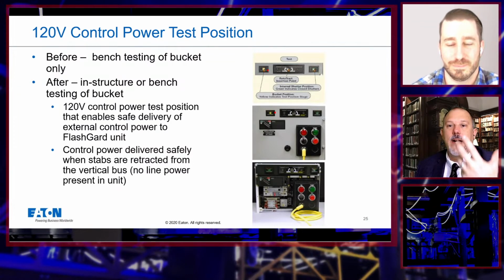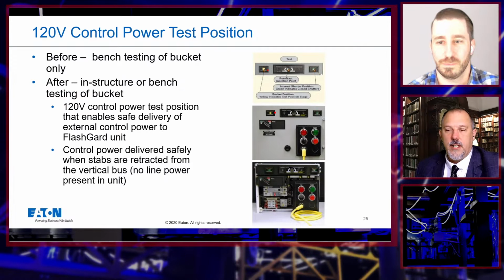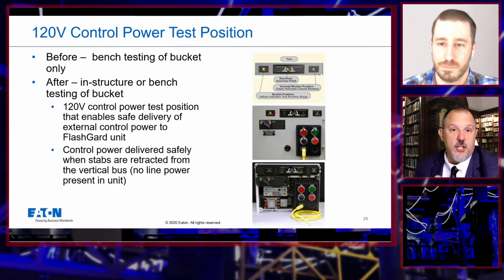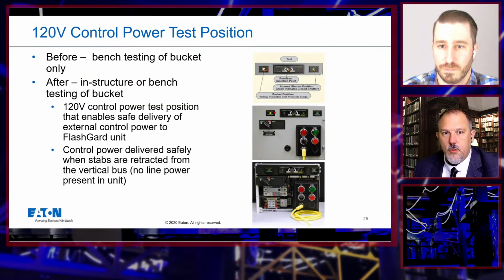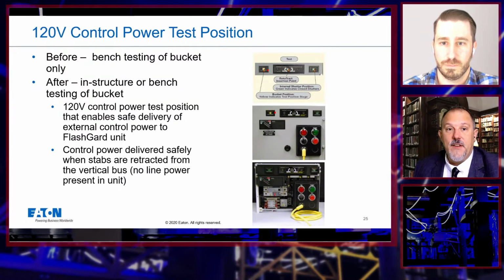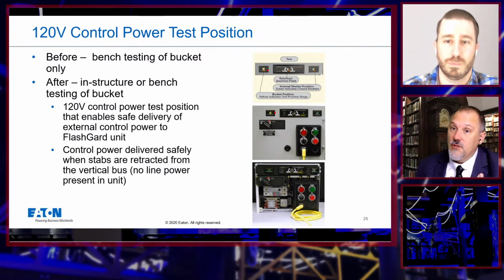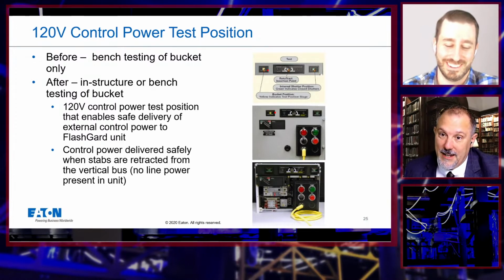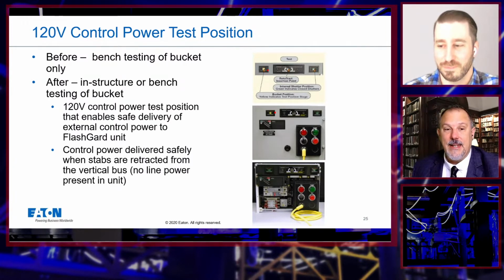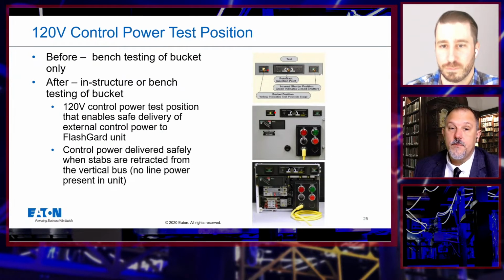We'll just summarize this; I do want to touch on the codes and standards, which we will do on the next call with Jim. I think Jim Dollard is going to help us with that one. But in any case, when you're doing the performance testing on first installation for a 240.67 or 240.87 requirement, we specifically put in there to follow manufacturer's instructions or do primary current injection testing, because there was a realization from the panel that our Bussmann fuse guys would love you to test every fuse when you first put it in so they can sell you another one, but that's not the intent, and that's not what we want you to do from a code perspective. You can test these technologies without damaging them.